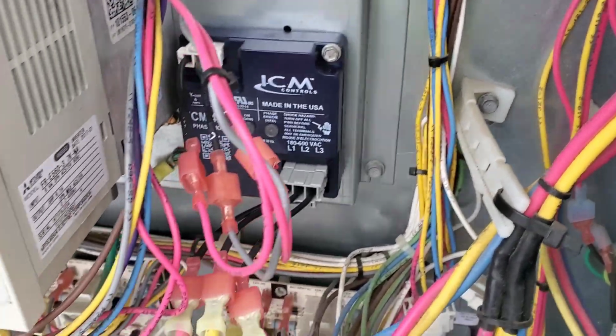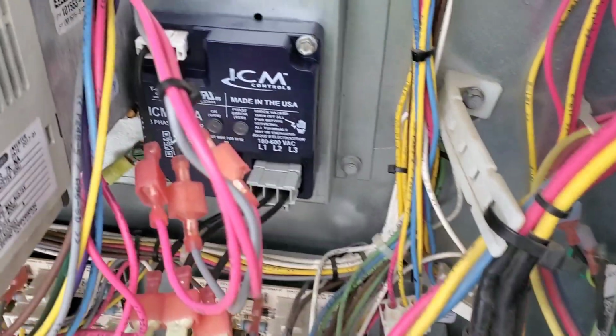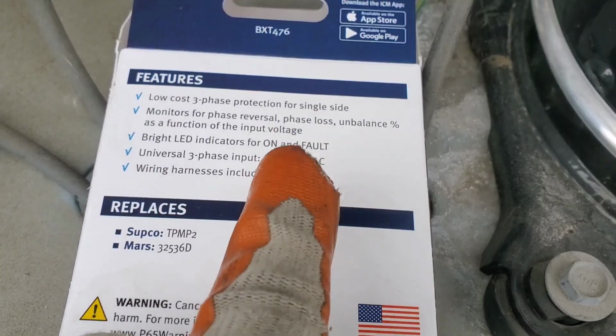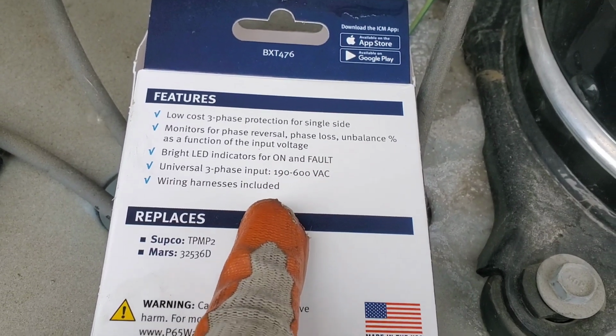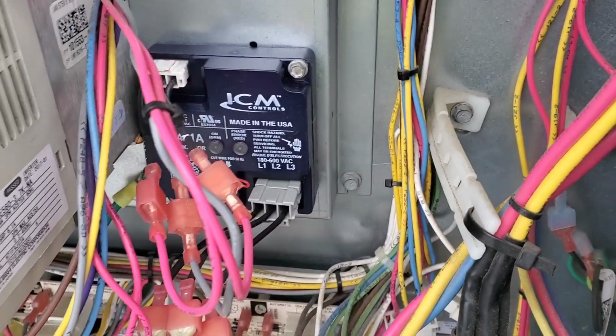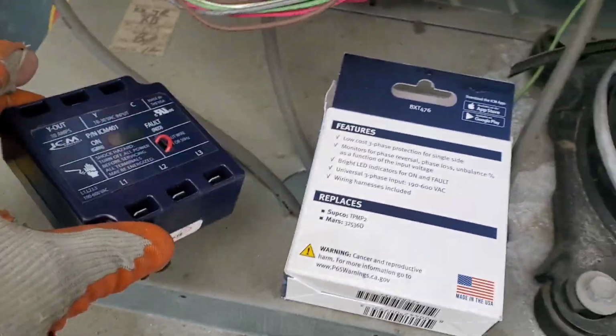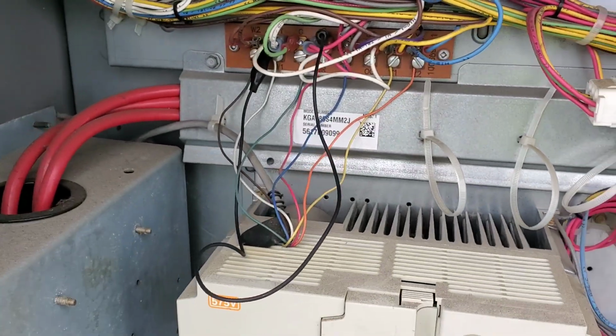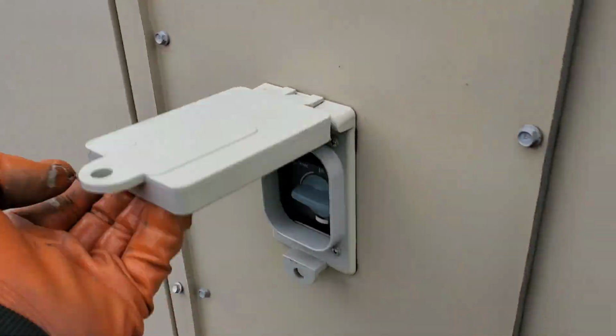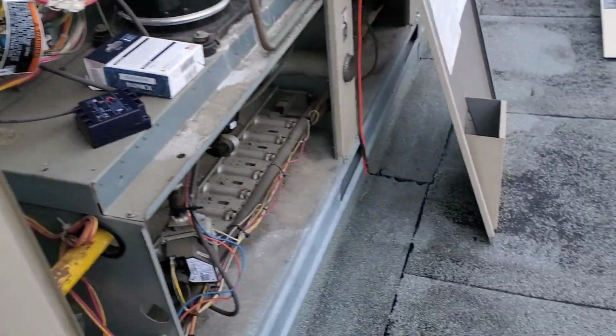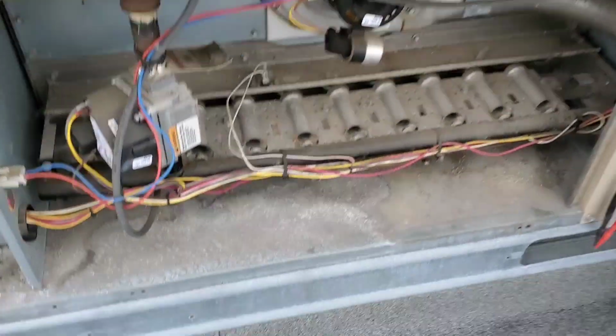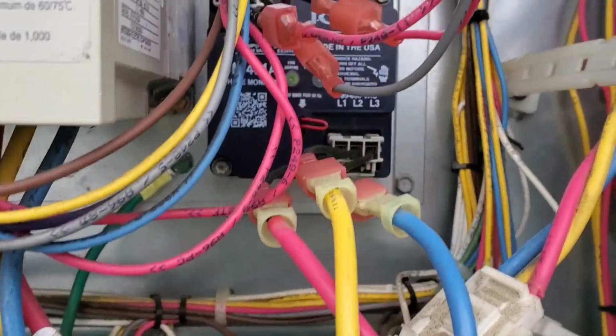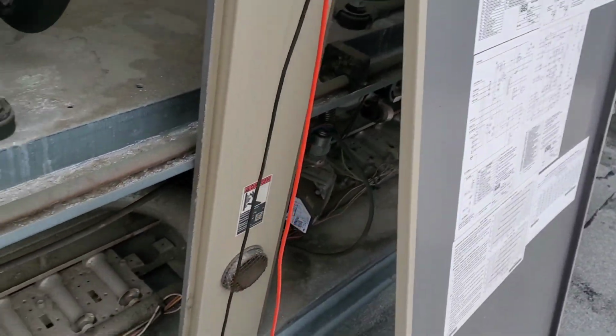Okay, so I have replaced the 3-phase monitor. Little bit different than the original, but it's the same thing. Rated for 190 to 600 volt. So this unit is 600 volt. So that's the old one. So already jumped out W1 to R. Okay, so we have green light here, if you can see, and blower motors, both blower motors started.